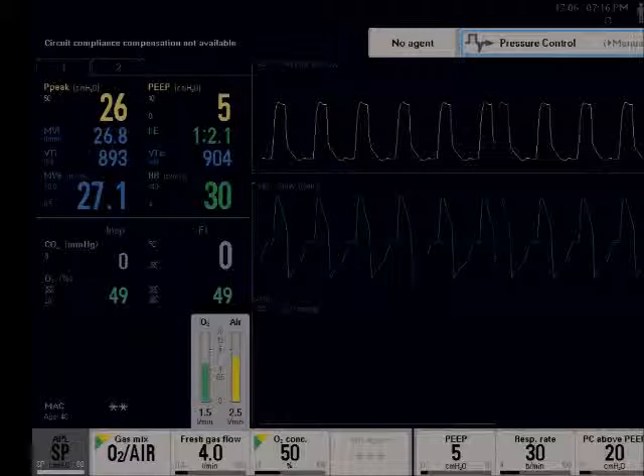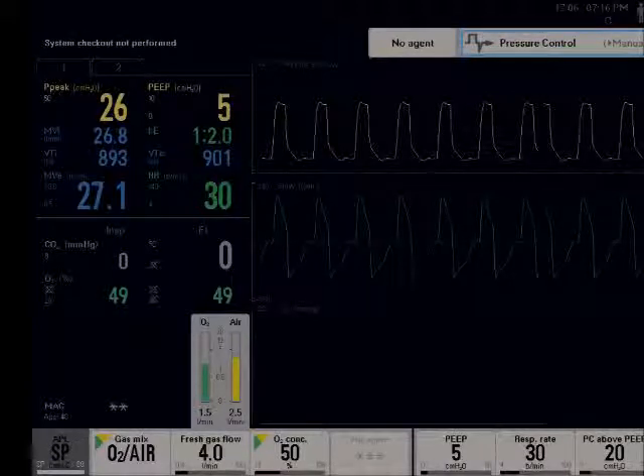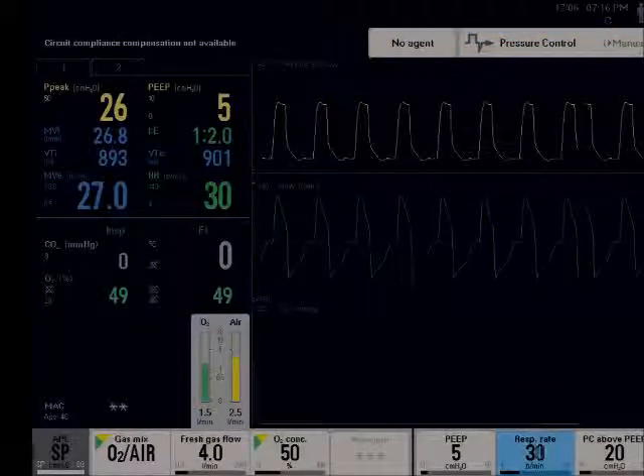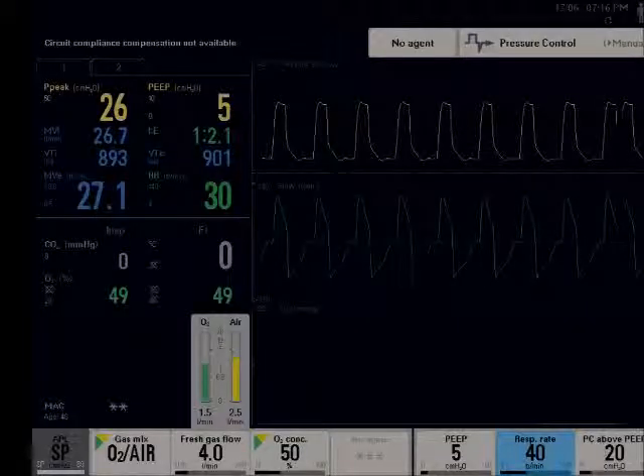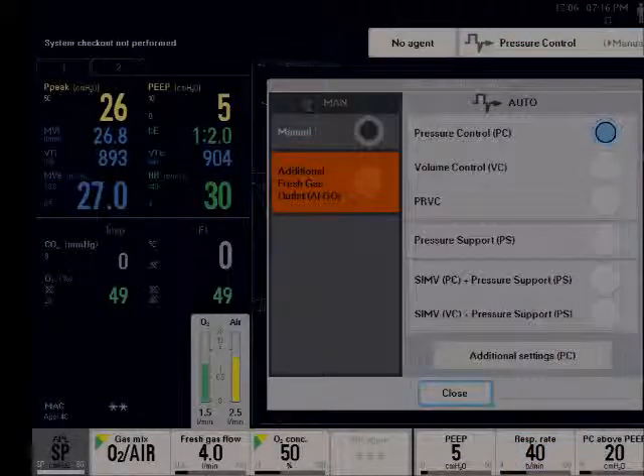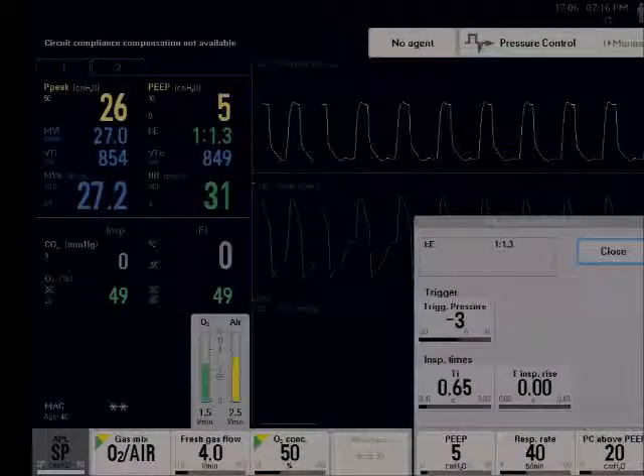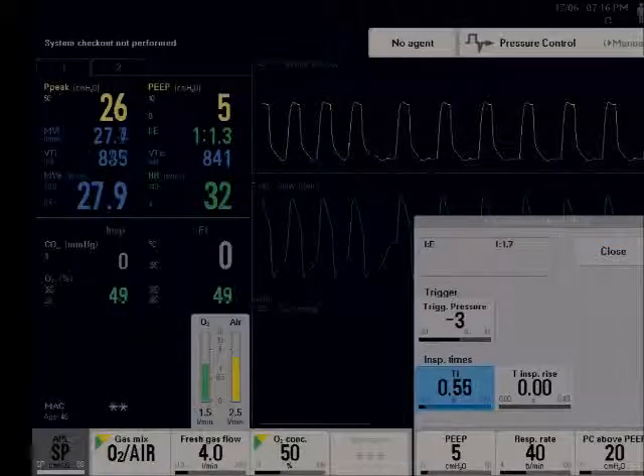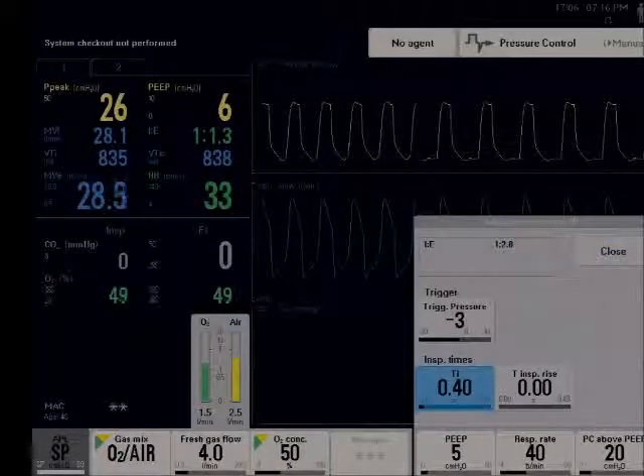And I will continue to increase the respiratory rate, which I'm doing now, to 40 breaths per minute. And let's go ahead and change my duty cycle again, or my I time, or my I time percent, so I have a 1 to 2 IE ratio again.